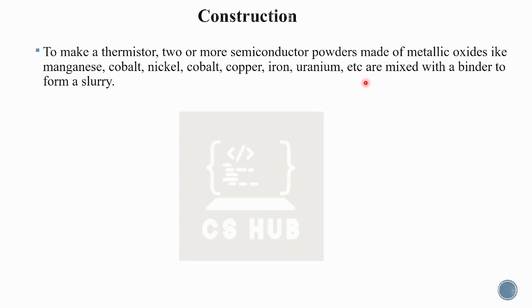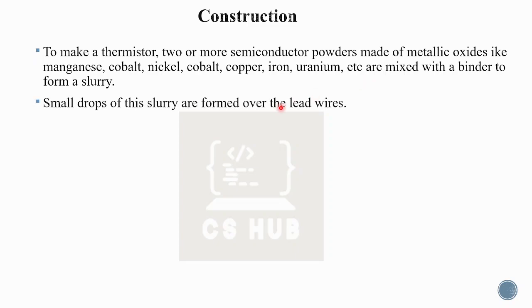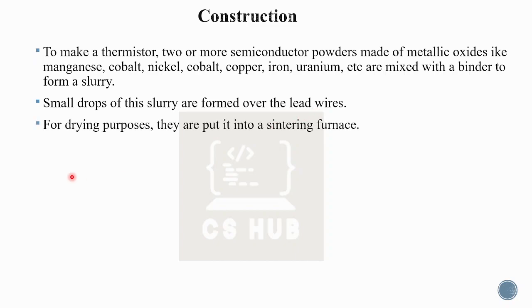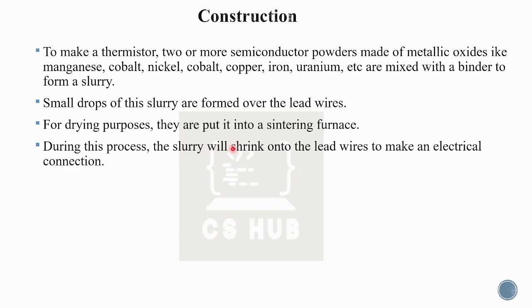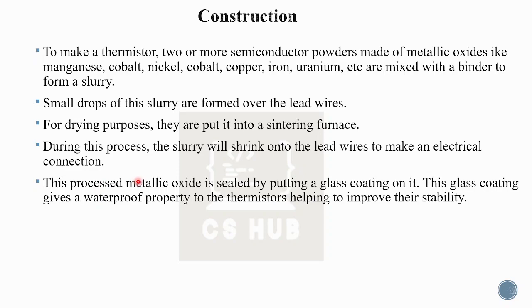The metallic oxides — cobalt, nickel, manganese, copper, iron — are mixed to form a slurry. Small drops of this slurry are formed over the lead wires. The bead is then shaped, dried, and placed in a sintering furnace. The metallic oxide is then sealed by putting a glass coating on it.